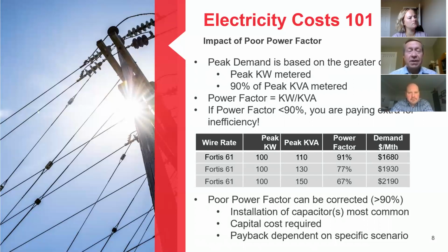So since the power factor calculation is kilowatts divided by kVA, if you have a power factor of less than 90%, you would pay for your peak demand based on the kVA you're using instead of the kilowatts. So what that means is, in effect, you are paying a bit of a penalty for operating less efficiently, since you're using more kVA than the wire's provider expects you to.